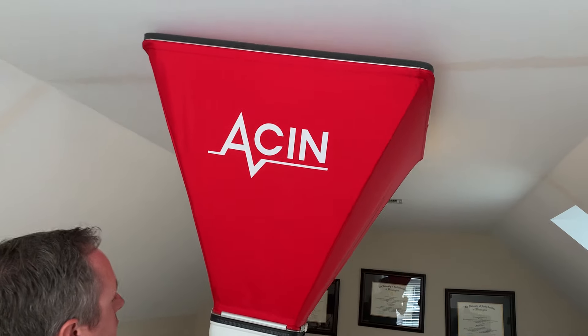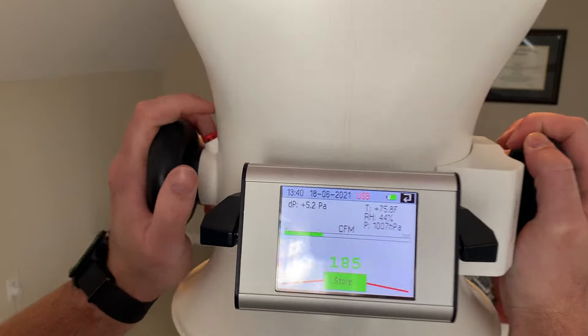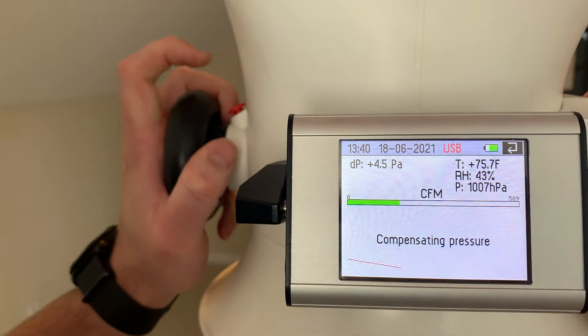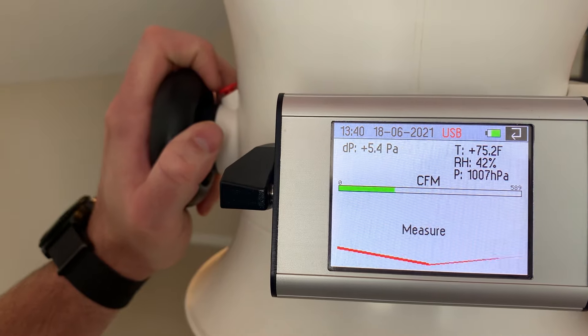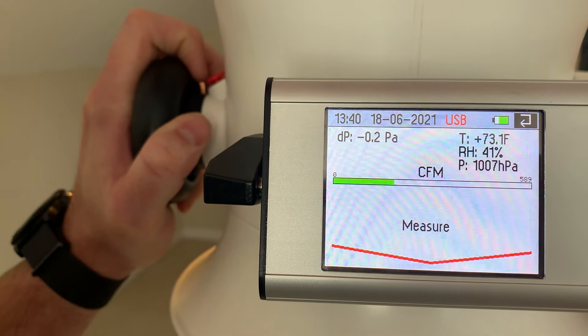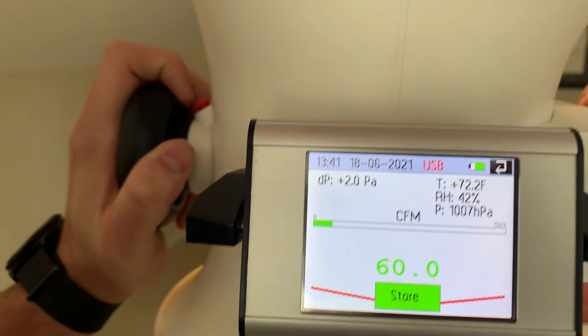Once we have the CFM that's being lost to the outside, we can apply that to the total CFM being delivered to the room. The best way to measure that is with the ACIN flow finder, which will get an accurate reading at the supply. The flow finder works similarly to a duct tester or a blower door — it has its own calibrated fan and high precision manometer built in, and it zeros out whatever pressure it feels and converts that to CFM.